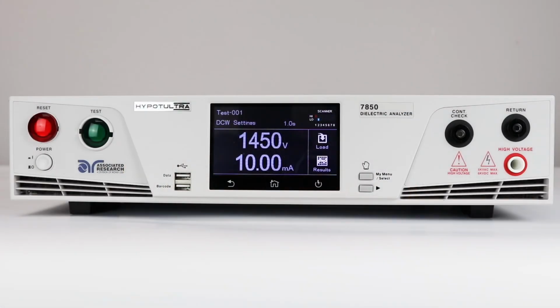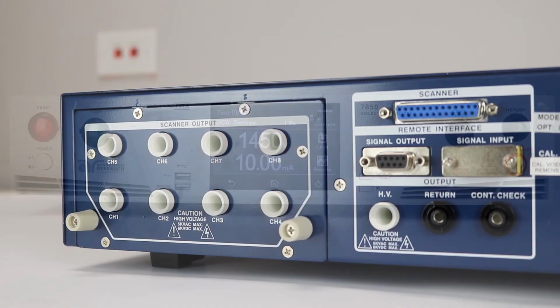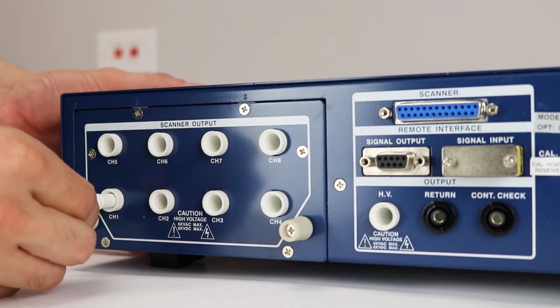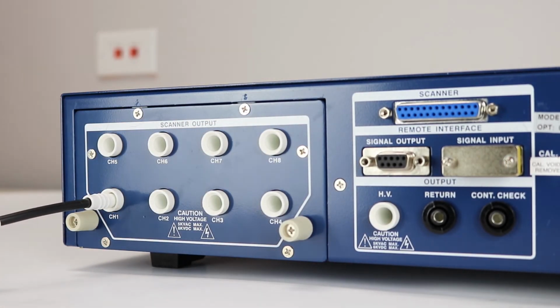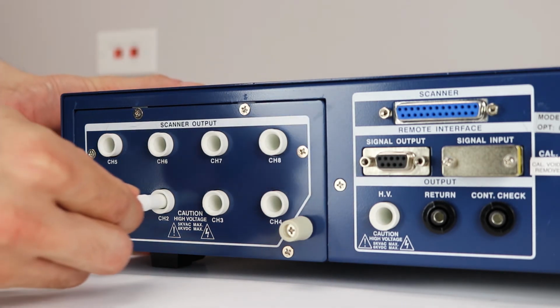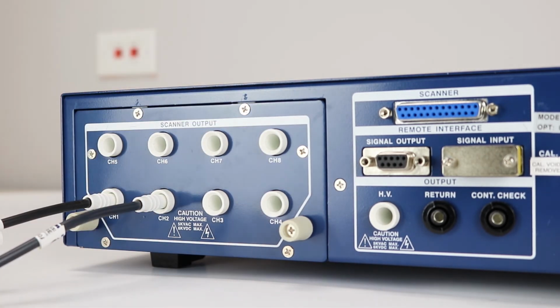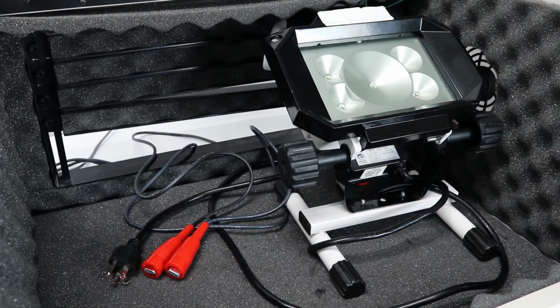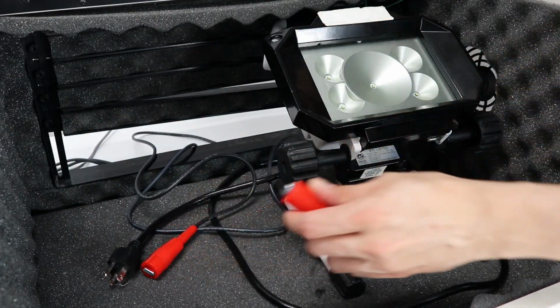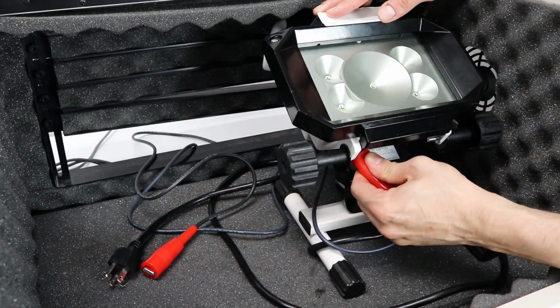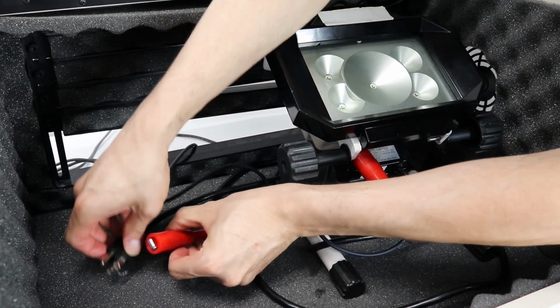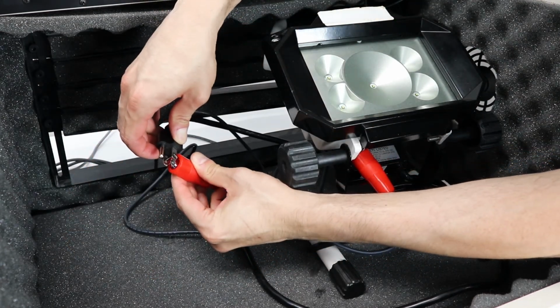We're going to show 2 separate test setups. The first setup will use the standard channels to run our DC Hypot test, and the second will use a universal style adapter box on a 3-pronged product. First, connect the DUT to the rear port scanner terminals. We've made up 2 separate high voltage connectors from the supplied high voltage wire and high voltage connectors. Since we're testing 2 points, we're going to connect the channels 1 and 2 on the built-in scanner on the DUT and the DUT chassis, respectively.